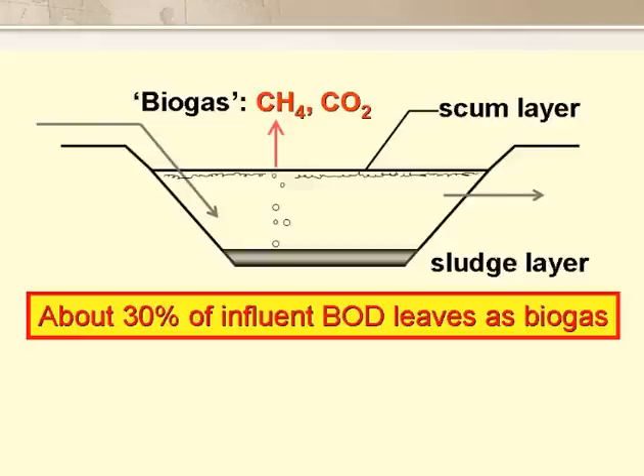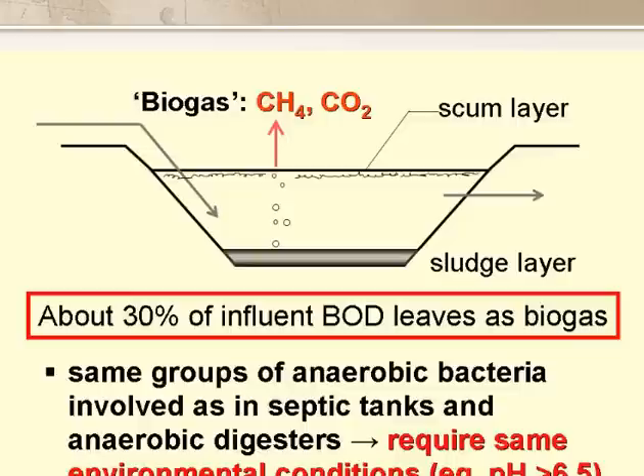Often around 30% of the influent BOD leaves the pond as biogas, CH4 and CO2. There are the same groups of anaerobic organisms in anaerobic ponds as in other anaerobic reactors, like septic tanks and anaerobic digesters, and they require the same environmental conditions, such as a pH above 6.5.